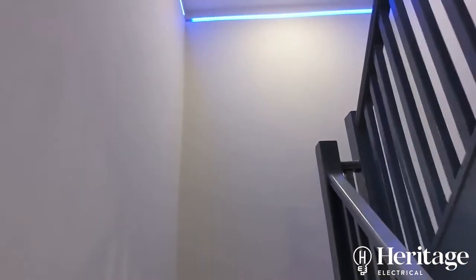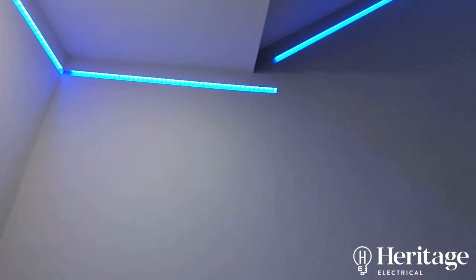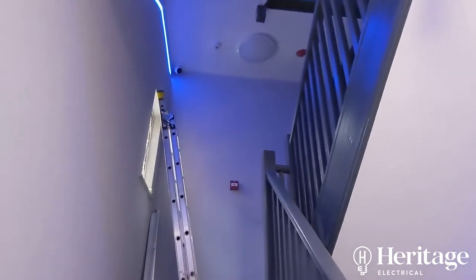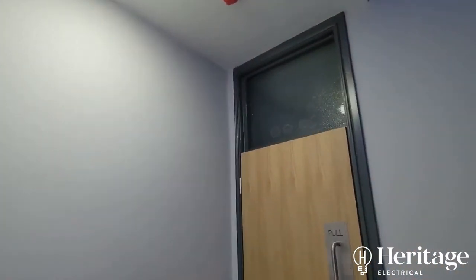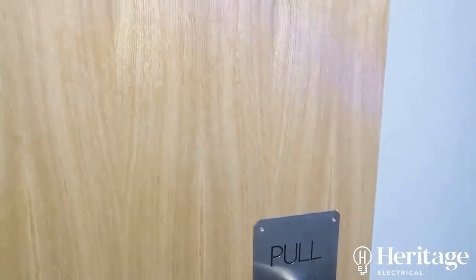All our emergency lighting is self-test. We've used Ansell emergency self-test bulkheads, so they test themselves every three months. As with all emergency lighting, there's the little indicator to show that the battery's charging. You can see aesthetically the carpet's come off the stairs and been replaced with a nice laminate. The LED tape is on PIR, separate from the bulkheads which each have a PIR or microwave sensor built into them.